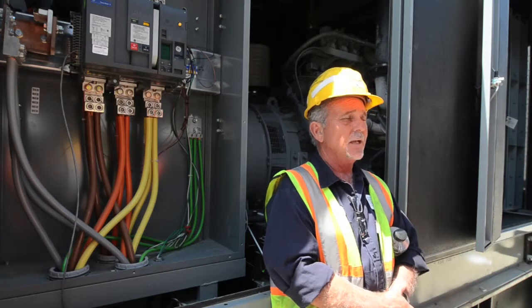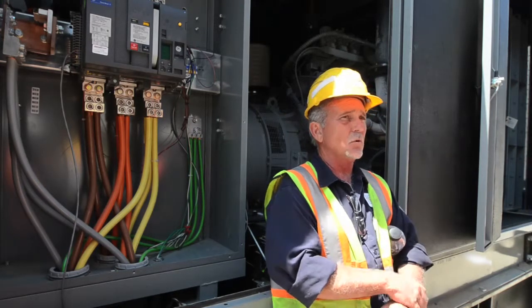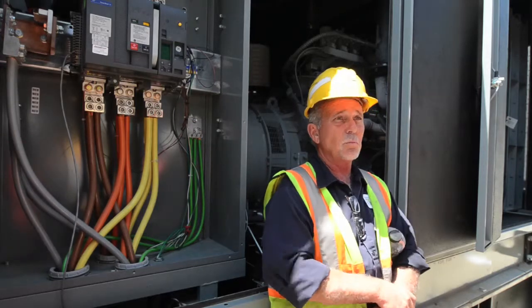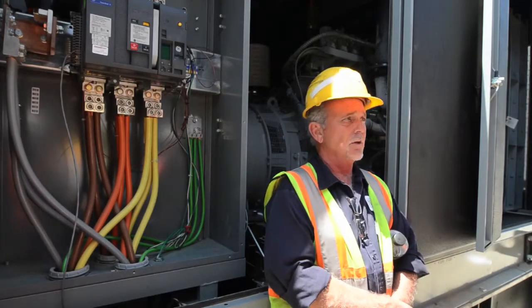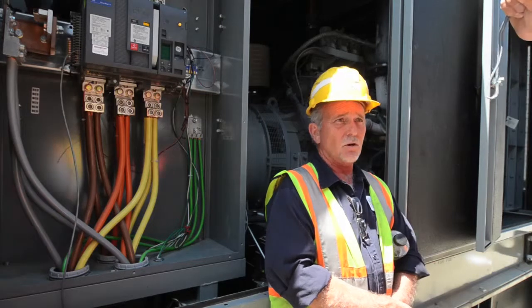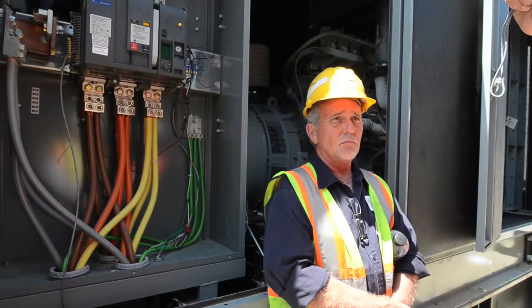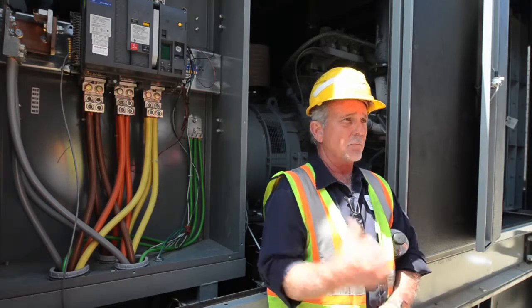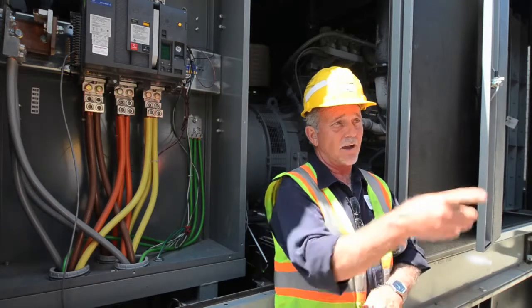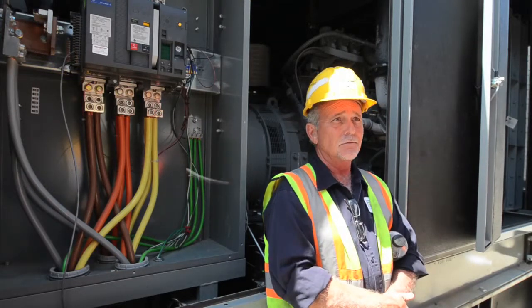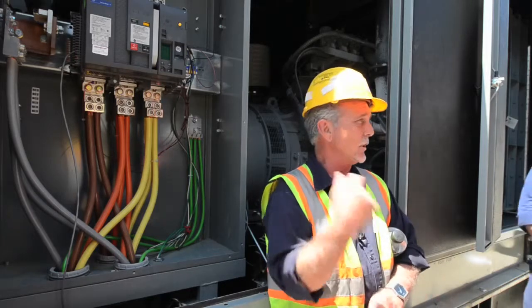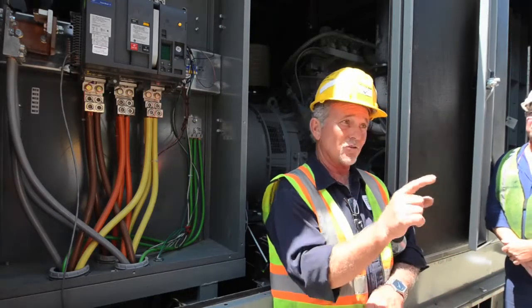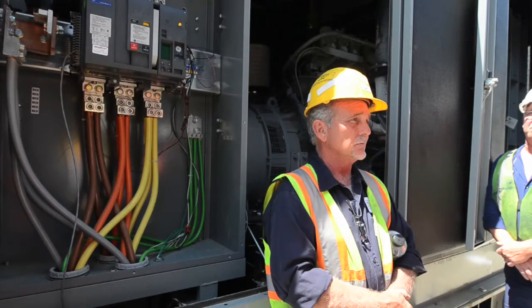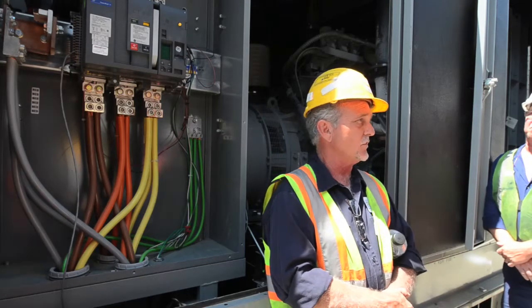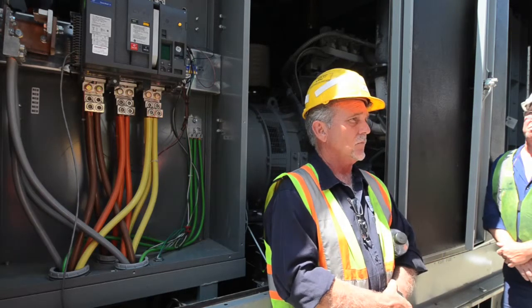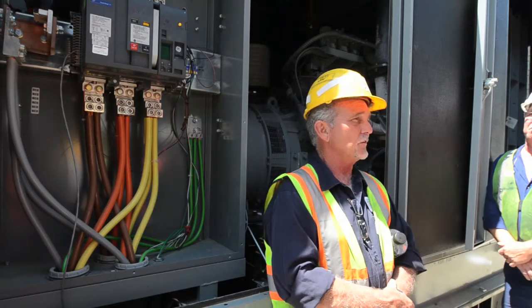That becomes a generator, and this is the reason that I was saying that it's so important that if you're going to have anybody work on these, please call us in. Okay, we know the system, we've built it, we know how it's going to respond to it. Because, technically speaking, if I hook up another generator that I close the breaker on, I can start this up and parallel it to it. I can't do it the other way around. I can't parallel your rental to this, but I can sure parallel one of these to a rental. Because that functionality still resides in these. So, that part of it's actually a really good system.